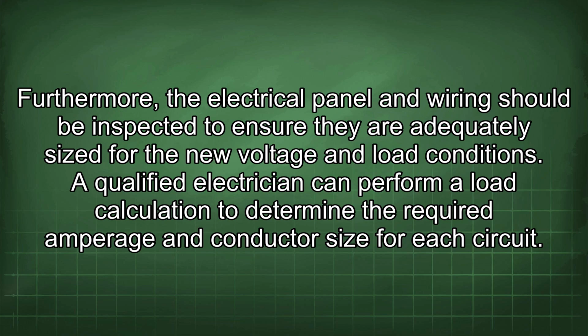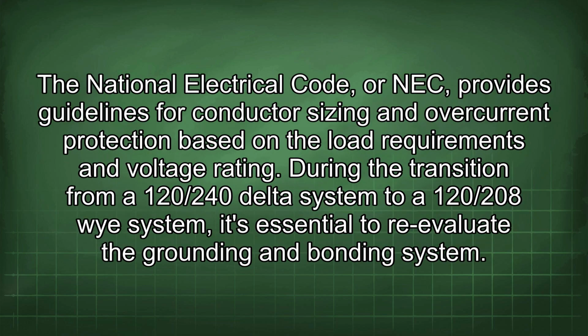Furthermore, the electrical panel and wiring should be inspected to ensure they are adequately sized for the new voltage and load conditions. A qualified electrician can perform a load calculation to determine the required amperage and conductor size for each circuit. The National Electrical Code, or NEC, provides guidelines for conductor sizing and overcurrent protection based on the load requirements and voltage rating.